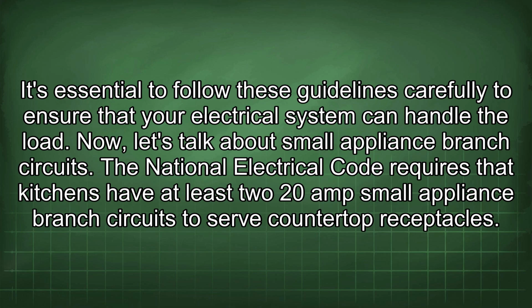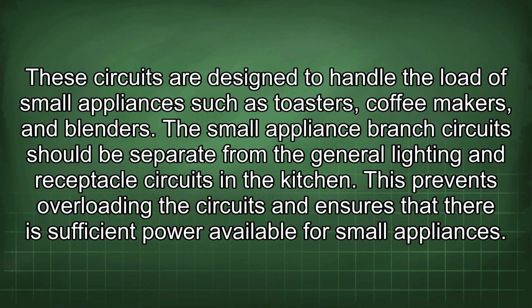Now let's talk about small appliance branch circuits. The National Electrical Code requires that kitchens have at least two 20-amp small appliance branch circuits to serve countertop receptacles. These circuits are designed to handle the load of small appliances such as toasters, coffee makers, and blenders. The small appliance branch circuits should be separate from the general lighting and receptacle circuits in the kitchen. This prevents overloading the circuits and ensures that there is sufficient power available for small appliances.